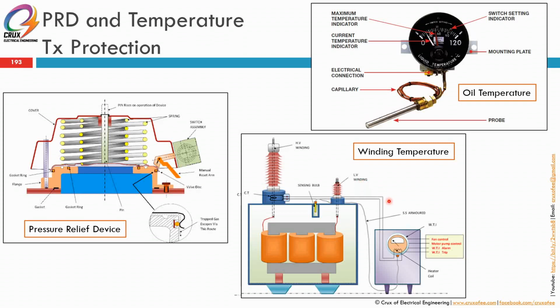But there's now more modern winding, there's more modern paper type that could withstand higher temperature, so it could be set higher. So if this is a winding using cast resin type, the setting will be higher, because cast resin can resist much higher temperature during its normal operation.